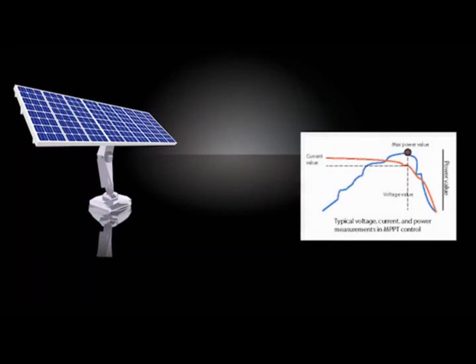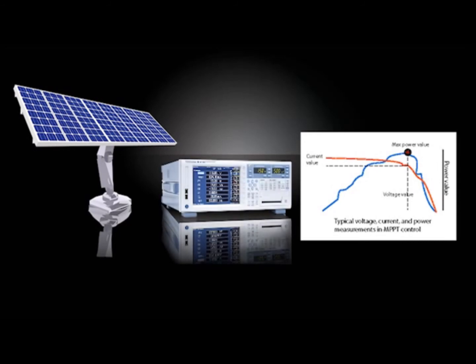In photovoltaic power generation, a maximum peak power tracking measurement is performed to maximize the harvested power generated by photovoltaic cells. To accomplish this, the WT1800 is capable of measuring peak voltage, current, and power values. The power integration function measures the amount of power sold or purchased in grid interconnection applications.